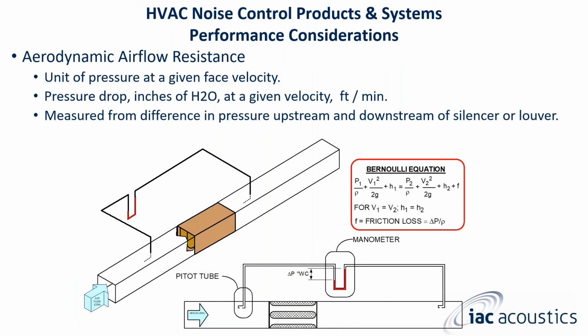Aerodynamic airflow resistance. This is a unit of pressure at a given face velocity, known as pressure drop, or PD. It is measured in inches of H2O, inches of water gauge, at a given velocity, feet per minute. It is measured as the difference in pressure upstream and downstream of a silencer and/or a louver. There you see in the red square the Bernoulli equation, so knock yourself out if you want to do that. If you want some help, I'll be more than glad to go over some good calculus and trigonometry with you as well.